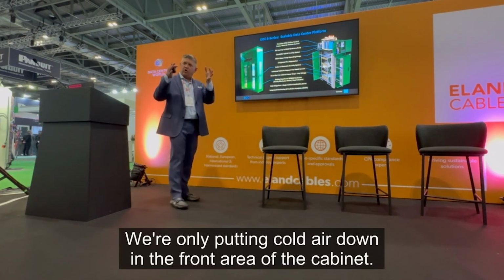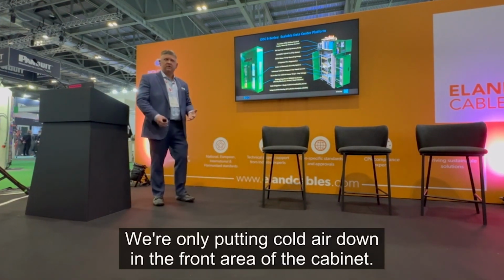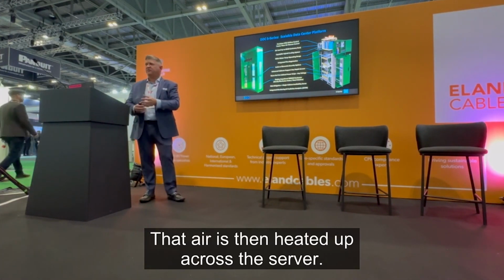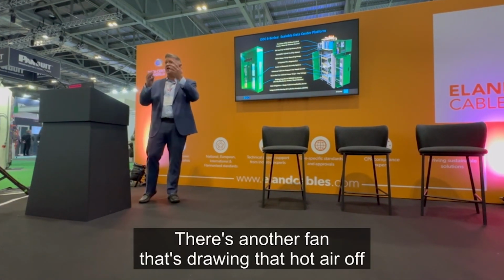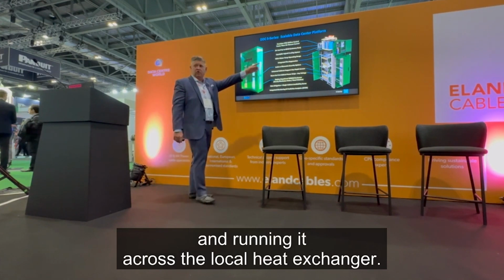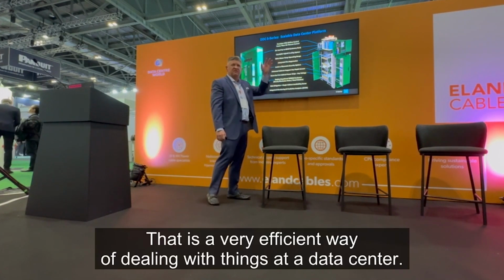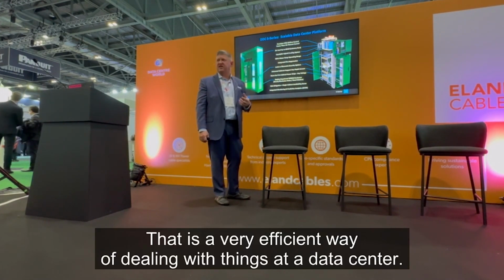So we're only putting cold air down the front of the cabinet. That air is then heated up across the server, and another fan draws that hot air off and runs it across the local heat exchanger. That's a very efficient way of dealing with heat inside the data center.